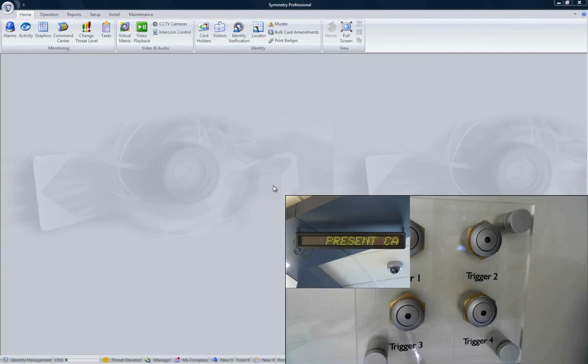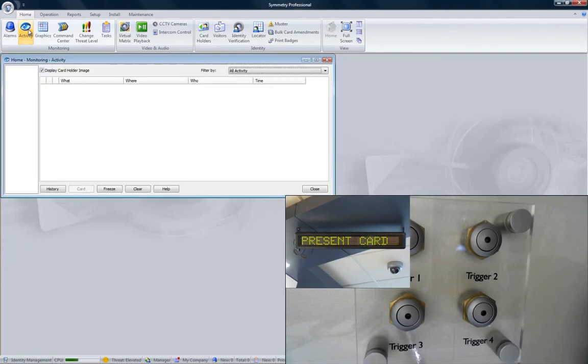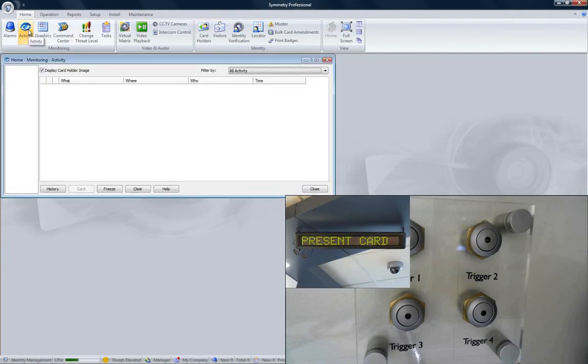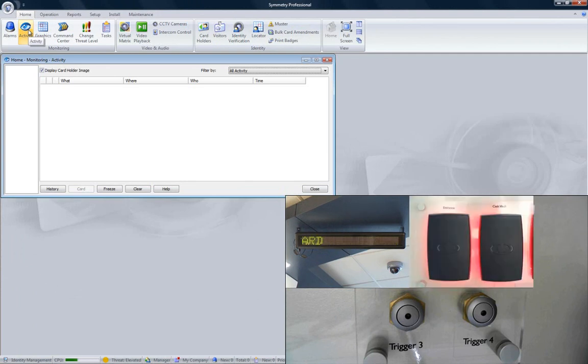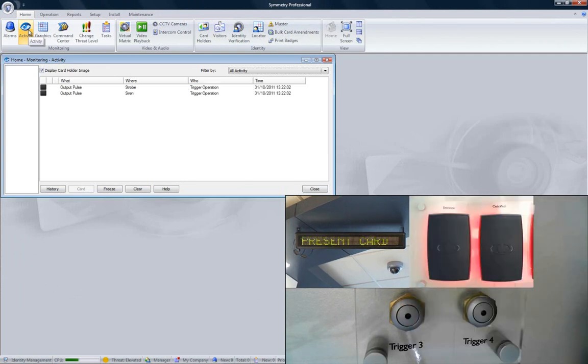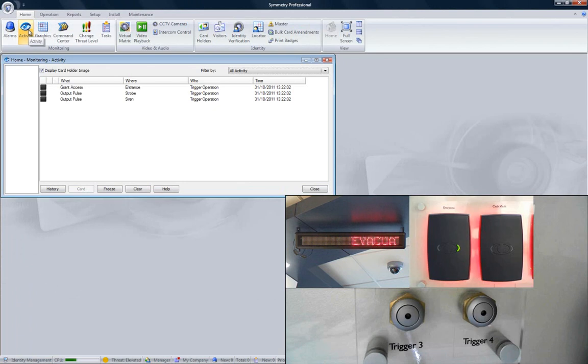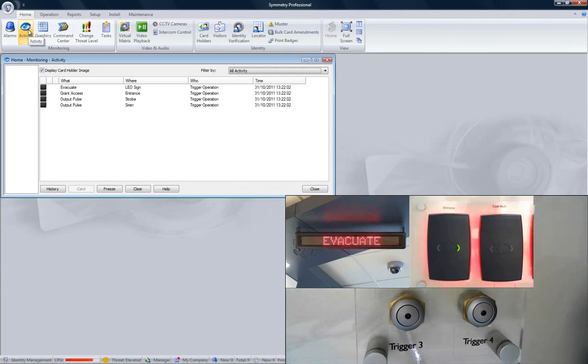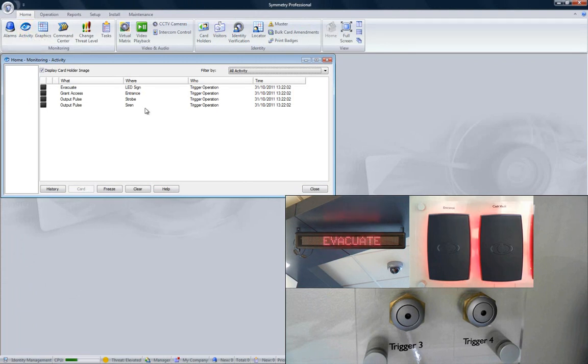Now let's see that trigger in action. Opening the activity screen allows us to see exactly what's going on. When the input is triggered, the activity screen shows what's happening, the siren and strobe outputs are pulsed, the LED message changes to Evacuate in red, and the green LED on the card reader comes on to show that the door has been released.